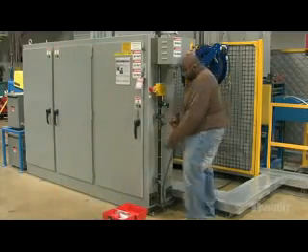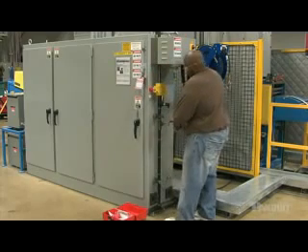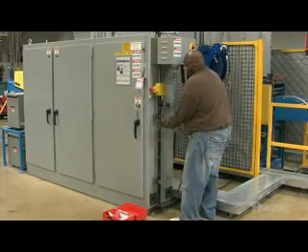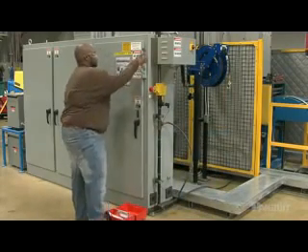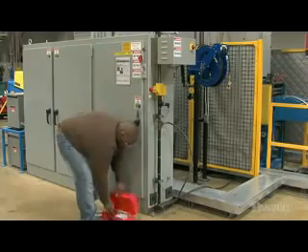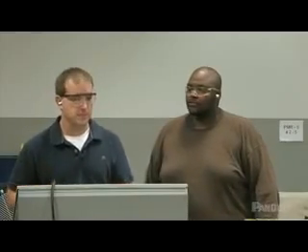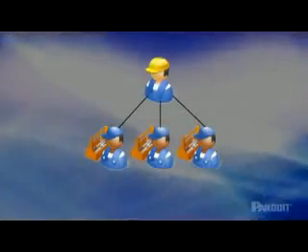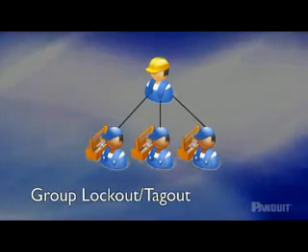Lockout-tagout devices can now be removed by the employee who applied them. If you are the last one to unlock, notify the area supervisor before restoring energy. When the work is done and all locks and tags are removed, restore energy to the equipment. Finally, it's a good idea to ask the responsible operator to test run the equipment to make sure it's operating correctly before you leave.